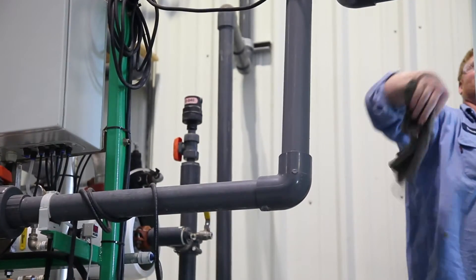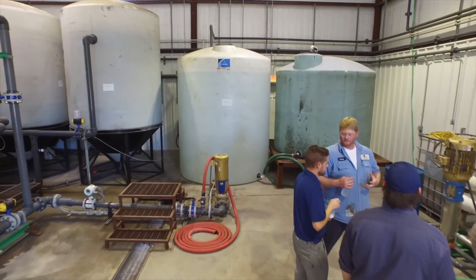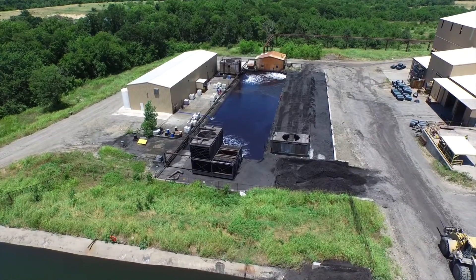It's really user friendly. Our reflux RO system runs at 40 gallons per minute. We run Monday through Friday, 24 hours. The spray water that we treat is actually the blowdown from eight different cooling systems, so it's the dirtiest water we have on site. And there it goes through the RO — 40 gallons a minute, 90 percent recovery.